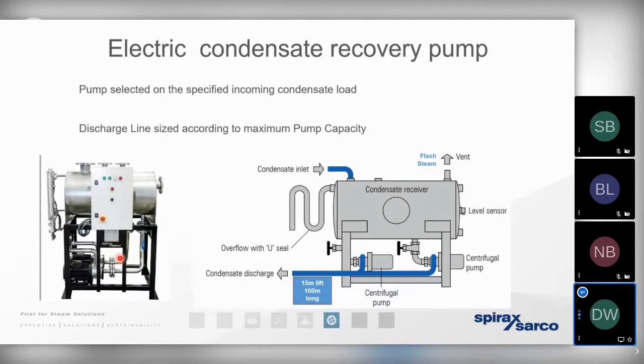We can use an electric condensate recovery pump. As the name suggests, it does require electrical installation because we will have centrifugal pumps, either on, off, or modulating, that sit underneath the condensate receiver. So the thing to bear in mind here is because we require electrical installation and because the pumps work electrically, it's important that we size the receiver to allow for that liquid condensate to fall to somewhere around 97 degrees atmospheric condition for two reasons.